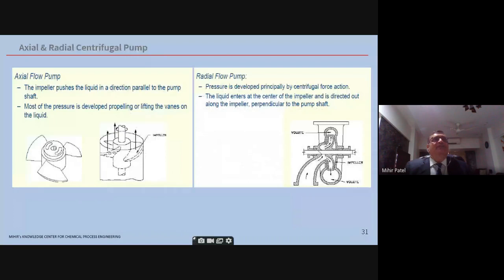You have two types, axial flow pumps and radial flow pumps. The majority of the pumps you'll see are the radial flow type, where the impeller is there. On the left-hand side are the axial flow pumps. These axial flow pumps are low head and very high flow capacity. Recently we did a project for one of my past companies for a client. The reactor had to have continuous circulation of the chemical to a cooler. So an axial pump was employed because it was basically a complete circulation and the head was very small, but the flow rate was huge to remove the exothermicity. That's a typical example of an axial flow pump.